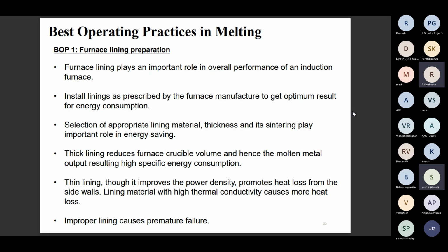The next one is thin lining. Though it improves the power density, it promotes heat losses from the sidewall, with lining material of high thermal conductivity causing more heat loss, and improper lining causes premature failure. So it is very important. Thinner lining is also dangerous, and thick lining also leads to more energy consumption. We have to optimize the lining thickness.